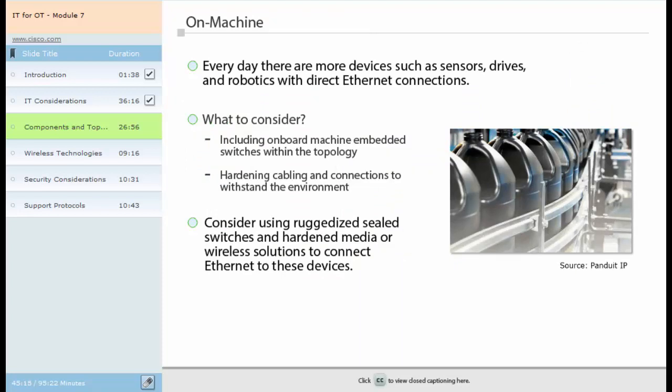The physical layer of a converged network extends down to the level of each automated device. The amount of devices with direct Ethernet connections, such as sensors, drives and robotics, increases continually. Two elements to consider are the onboard machine or device itself and how the embedded switches of the machine will fit into the topology. For connections and wiring installed on machines, the exposure at different stages of an automated process needs to be taken into consideration. Devices may be located in areas exposed to extreme temperatures and dust particles, and may also be in constant movement. Consider using ruggedized sealed switches and hardened media such as M12 connectors or sealed RJ45s to connect Ethernet to these devices.